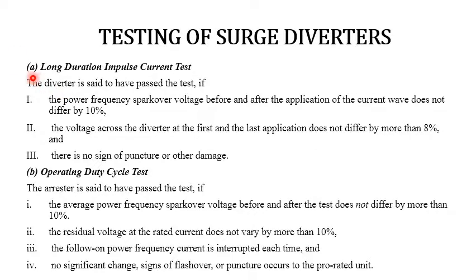Next is the long duration impulse current test. This test is also done on prorated units, the same 3 to 12 kV. The circuit used for generating a rectangular impulse wave consists of an artificial transmission line with lumped inductance and capacitance. The duration is 2(n minus 1) multiplied by the root of LC. As per the specification, 20 applications are made with the specified current in 5 groups, so that the interval between successive applications is about 1 minute.